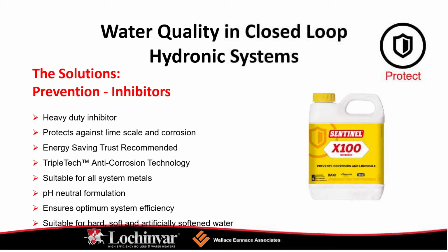So without further ado, let's introduce the X800 inhibitor from Sentinel. So this is neat. It's simple. It's a twist and dose adapter, kind of a rapid dose is what we call it, and that's certainly what this is. 1 can is usually sufficient to treat a typical domestic central heating system. It can discharge into the system in 30 seconds. We don't need to depressurize or cool the system. And multi-location application combined with the twist and dose system. And again, very simple. Allows for 4 dosing methods.